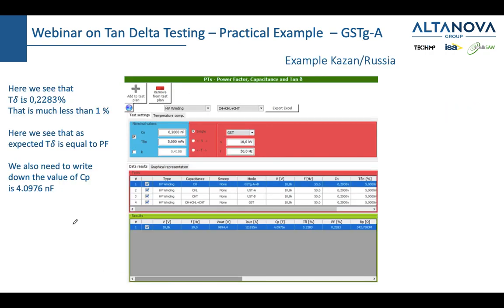This is an example of one test which we did in Russia. It was not a small transformer. It was about, if I'm not mistaken, a 45 MVA transformer. This is the report, but what I wanted to show you is, after you've done your measurement, for example, we measured CH, we measured CHL, and we measured CHT. So this was a transformer with primary, secondary, and tertiary winding.